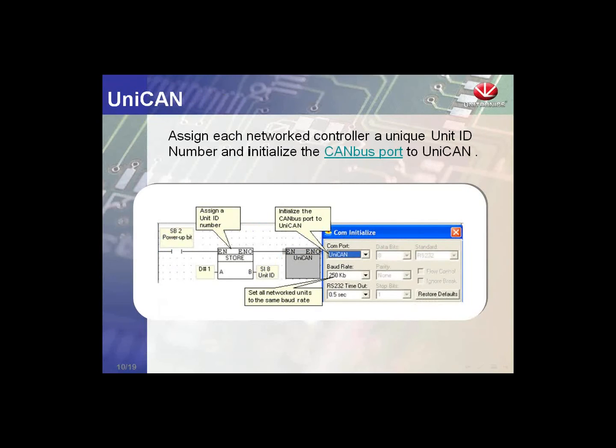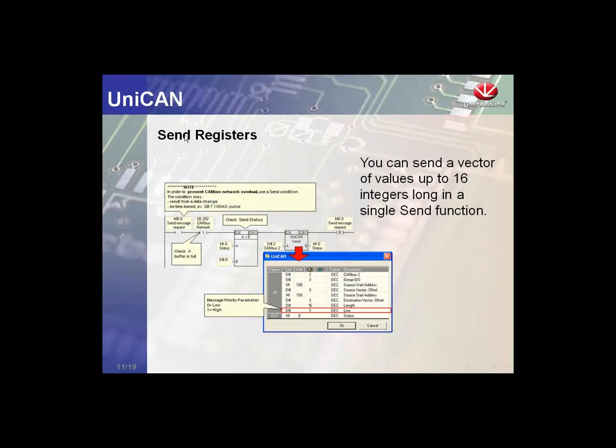We will look at the UNICAN functions available. The first is the CAN bus setup: under com initialization, we select UNICAN from the dropdown and select a baud rate — we will use 250 kilobits, good for up to 250 meters. We also assign a unit ID number, which is how we address each specific controller, between 1 and 60. The first UNICAN function block is the Send Registers block: we can send a message to any controller, send up to 16 memory integers, and set the priority as high or low.